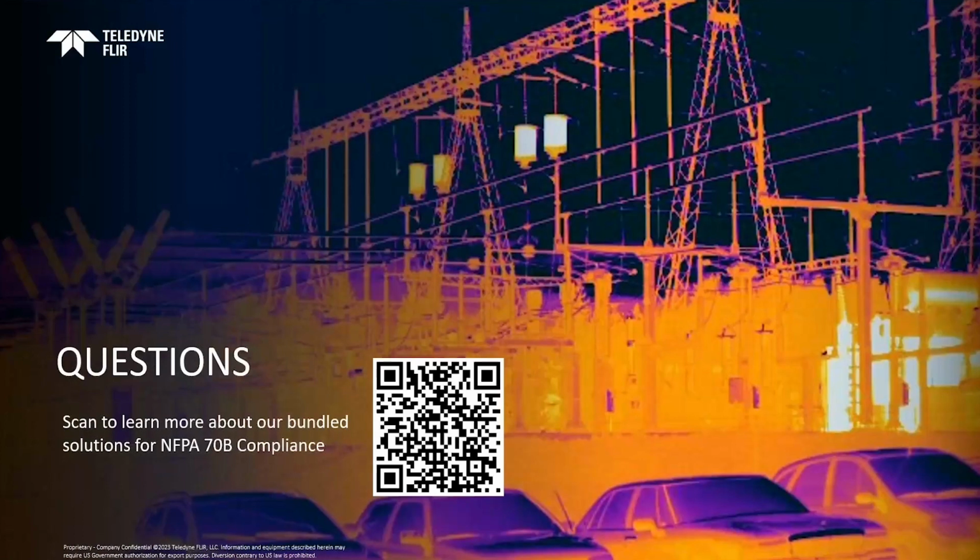Yeah, and having reviewed that documentation, there's definitely very specific guidance there. And as you mentioned, infrared is listed throughout. If you look at the frequency schedules for maintenance activities, it's broken down very specifically by asset class, so the different types of electrical equipment.